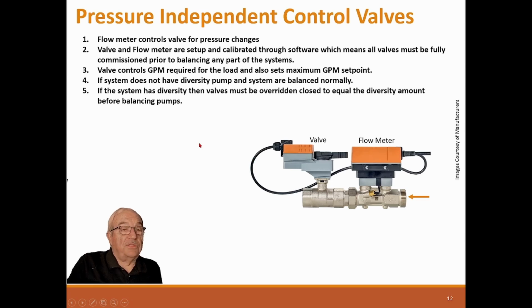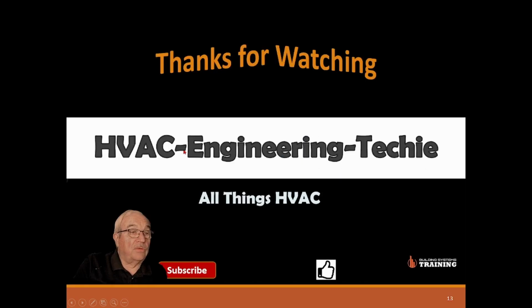Where I've had problems with these in the past is where we had two or three 3-inch, and then we had a bunch of regular valves, not pressure independent valves, for fan coil units and the rest of the system. This was several years ago, and these were early. They had a problem being stable. They would begin to hunt, because I think the other valves were doing their thing, and this one was trying to be pressure independent, and it was hunting all the time. Eventually, we were never successful in getting them to work correctly. We had to remove them. They were Belimos also, but we just couldn't make them work.